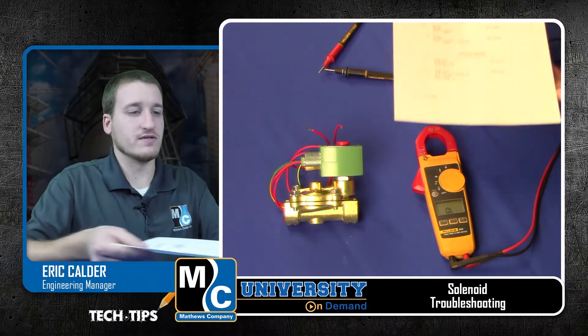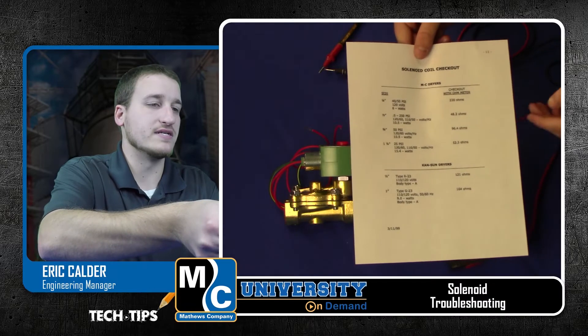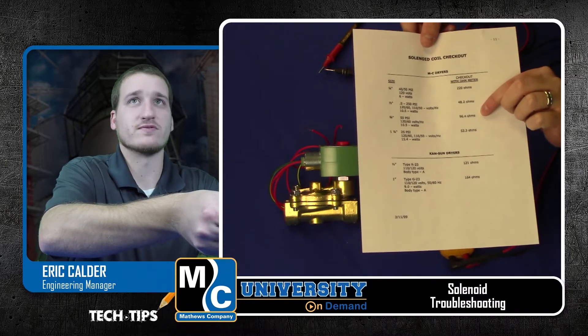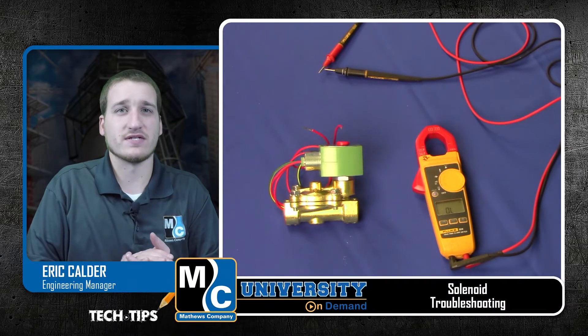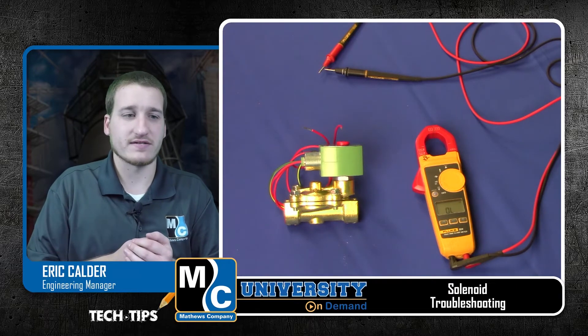Here I have a chart that we'll include in the notes under this video. On this chart, we can see that a 3/4 inch solenoid should have 96 ohms — we're very close to that with 93. What we're looking for when we test these solenoids is to see if we have either an open circuit or significantly higher resistance than we're expecting.